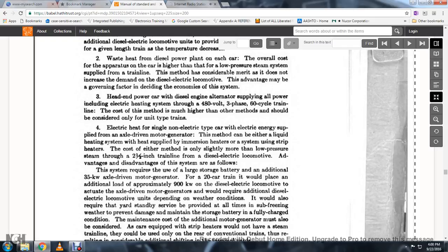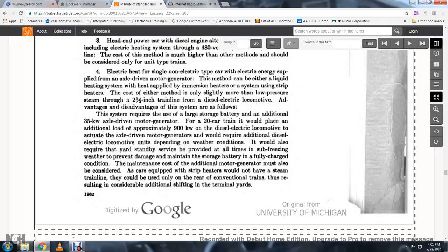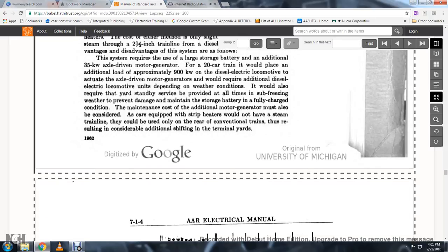For electrical heating for single non-electrical type cars with electrical energy supplied by an axle-driven motor generator, the method can use either a liquid heating system with heat supplied by immersion heaters, or a system using strip heaters. The cost is only slightly more than low pressure steam through the 2¼-inch train line for the diesel-electric locomotive. The system requires a large storage battery and an additional 35-kilowatt axle-driven motor generator for a 20-car train, placing an additional load of approximately 900 kilowatts on the diesel-electric locomotive. The axle-driven motor generator would also require standby service to prevent damage in freezing weather and to maintain the storage battery fully charged.